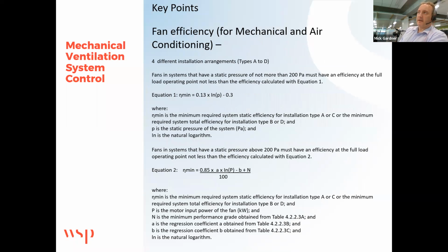So one thing they've introduced now is calculating fan efficiency, or motor efficiency for fans. And being from the UK, obviously I've gone through with Part L on the requirements we've had to do for that, where we've had tables. It's all been tabulated on the fan use, and whether it's an air handler unit, and it gives you a targeted specific fan power. Here you have to calculate the required fan power based on the design of the system and the type of fan you're using. So it's getting a bit more complicated. They've developed 4 arrangements for a fan. So you've got, for example, a type A, in this arrangement where a fan is installed with a free inlet and outlet conditions. So that's like a window or wall fan. Type B is an arrangement where fans installed with a free inlet and ducted.